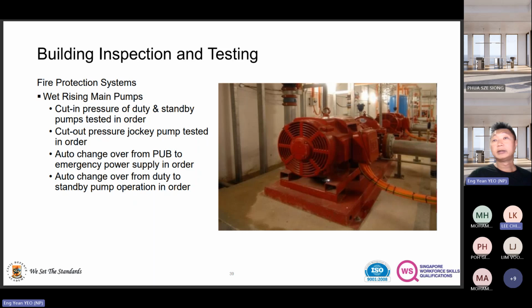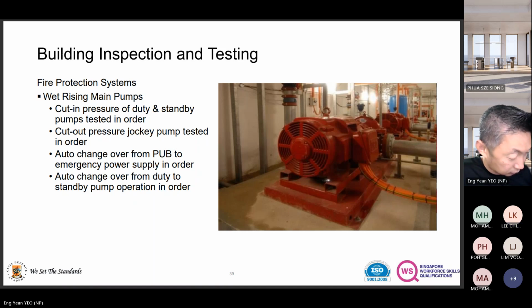Right? Just to check, you said the pipe is actually 180 PSI before the jockey pump cuts off. Am I right to say? Yes. Okay. Then initially you said the pipe is at 180 PSI pressure, right? But initially when you start the whole thing, you will start the jockey pump before it cuts off, because the pressure is not there yet initially. Am I right to say?